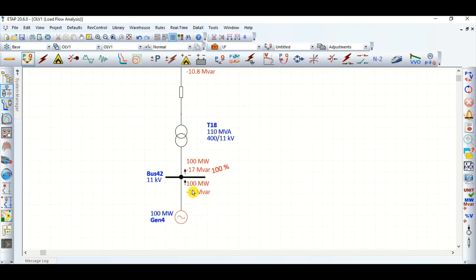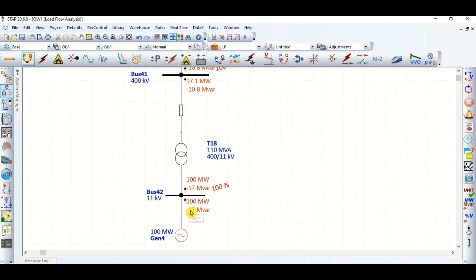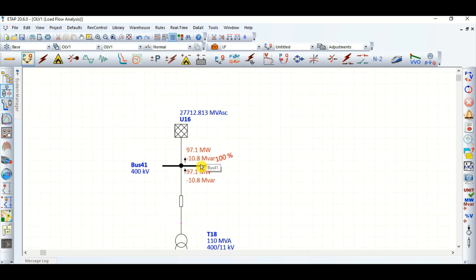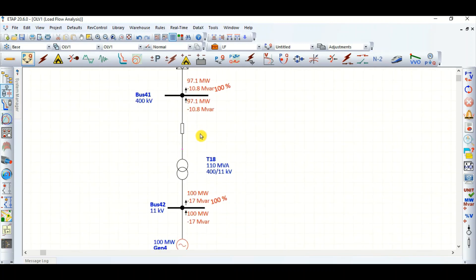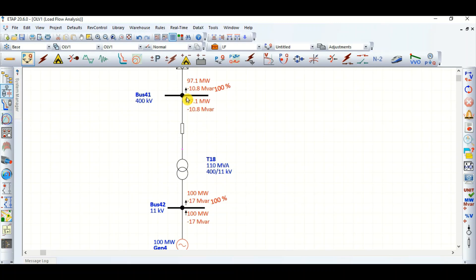The question is: why is the generator absorbing reactive power rather than supplying it towards the grid? It is because there is a transmission line — not a cable — and because of the capacitive effect of this transmission line, reactive power is flowing towards the generator bus, towards this 11 kV generator bus.